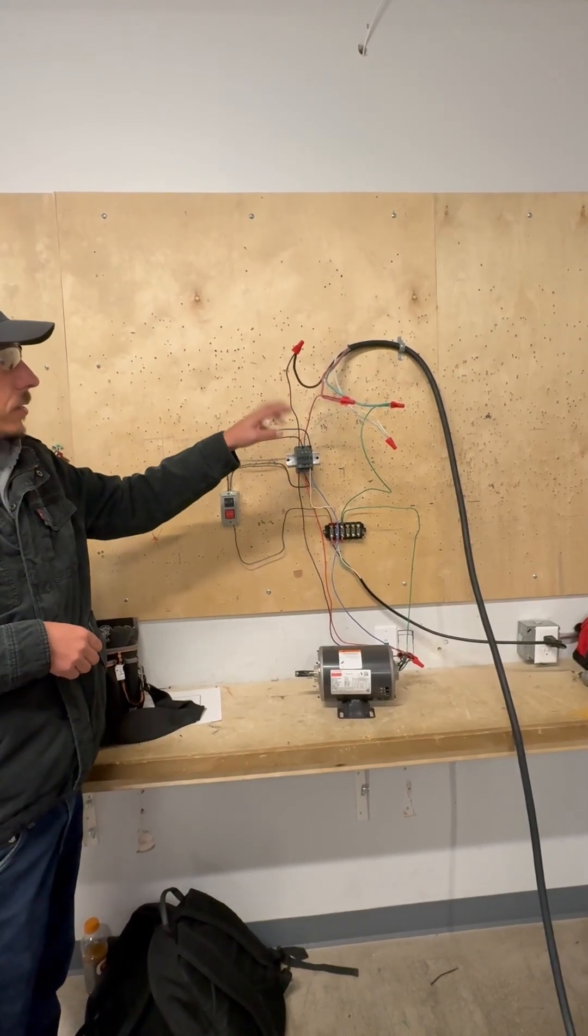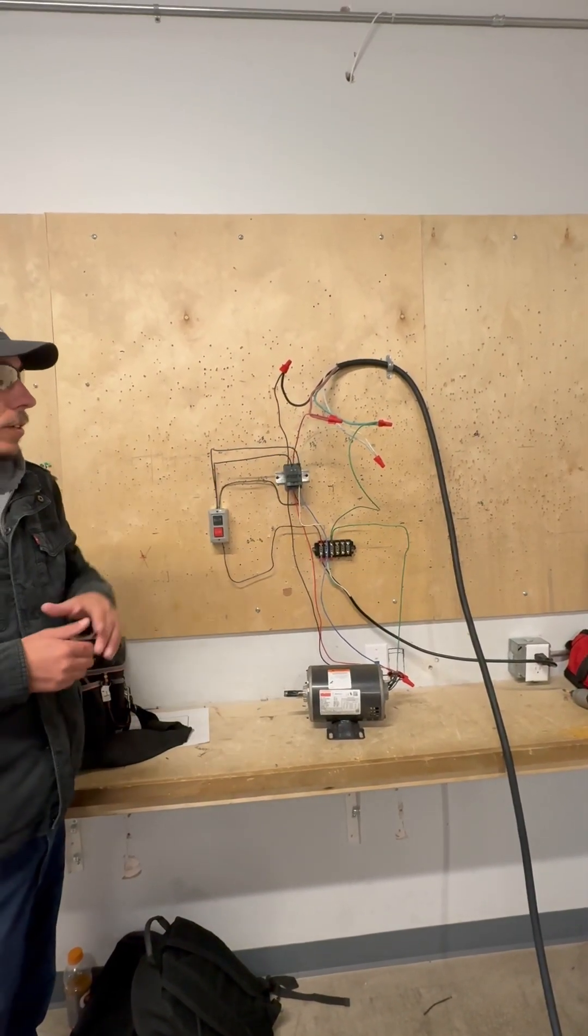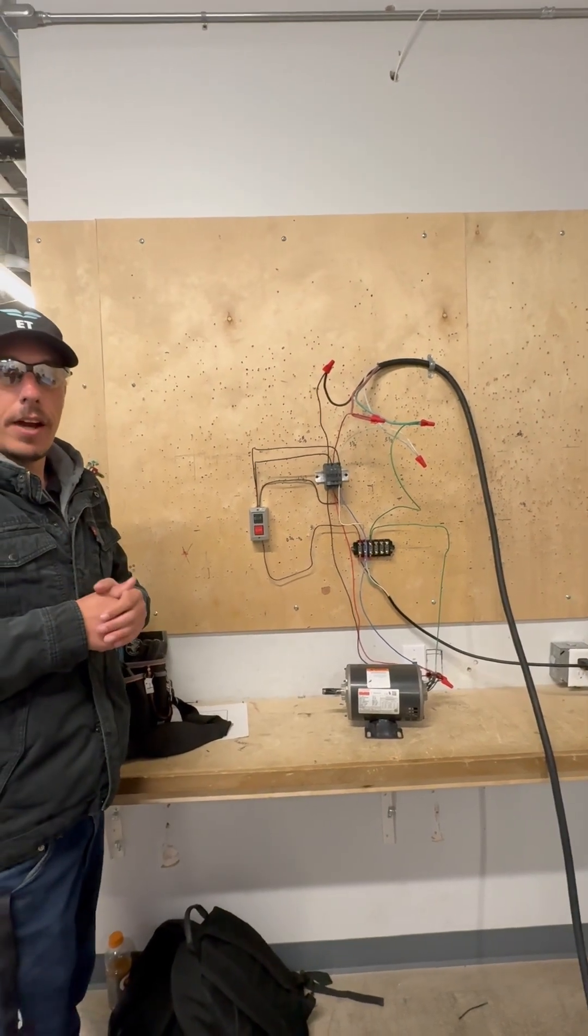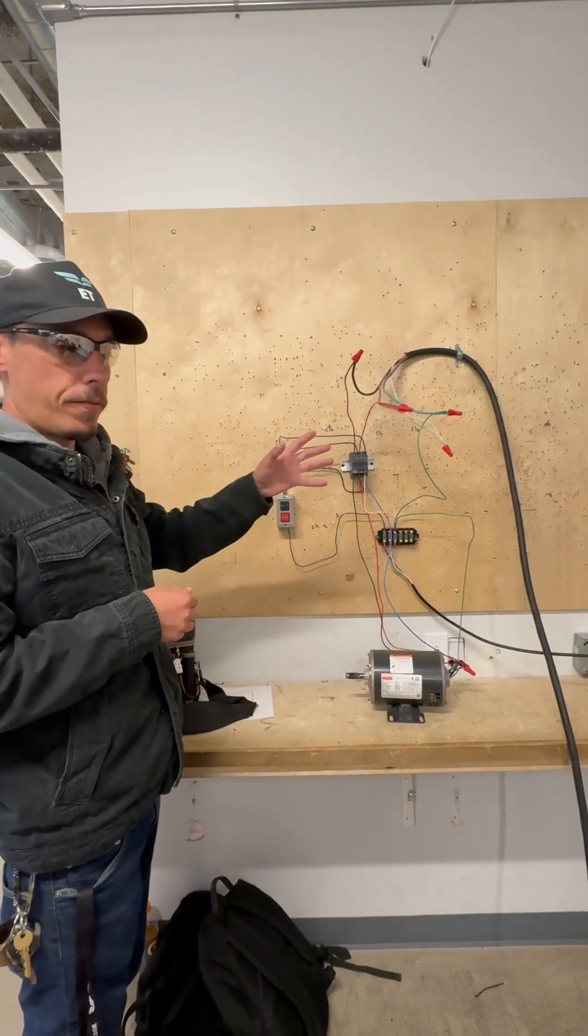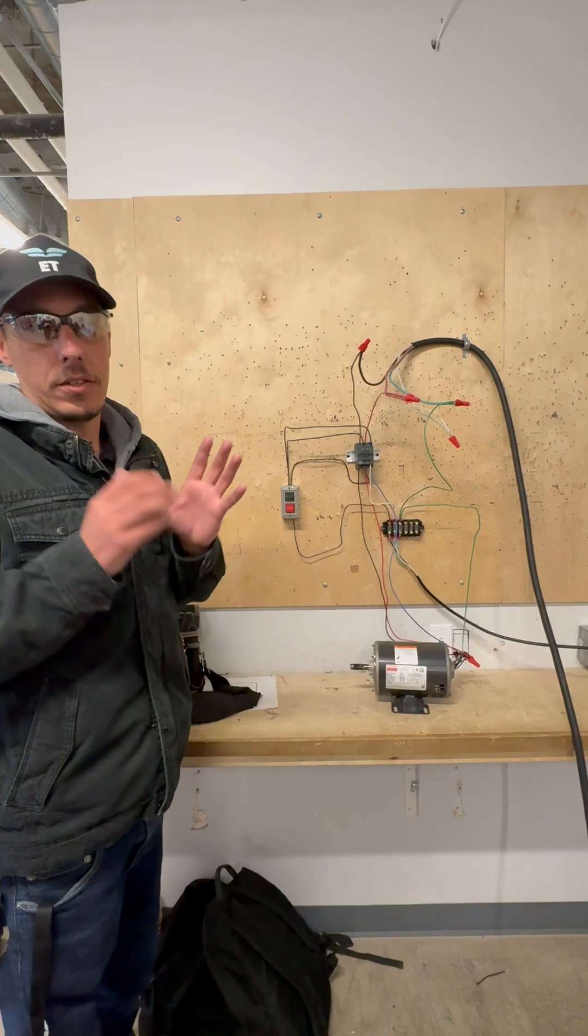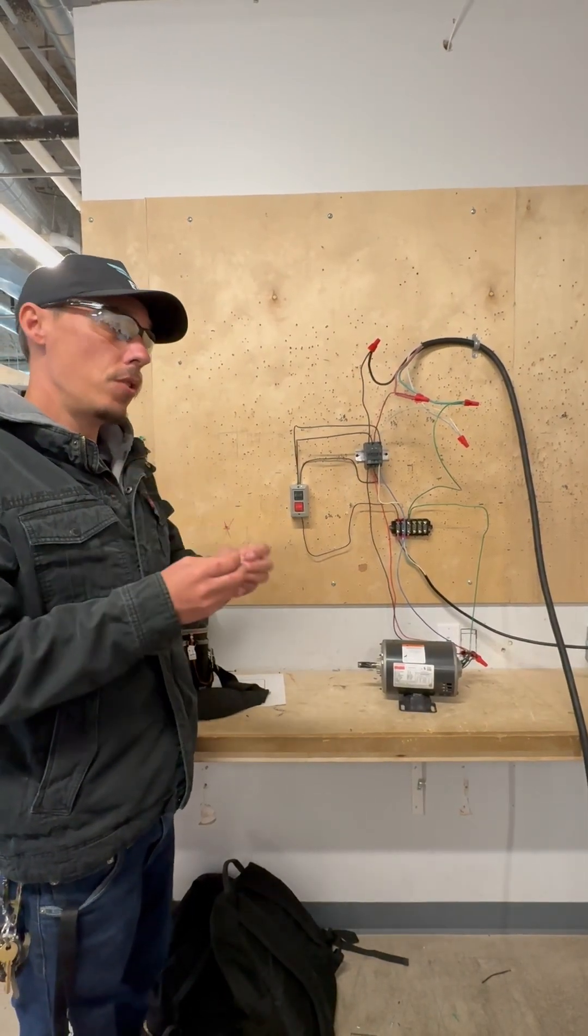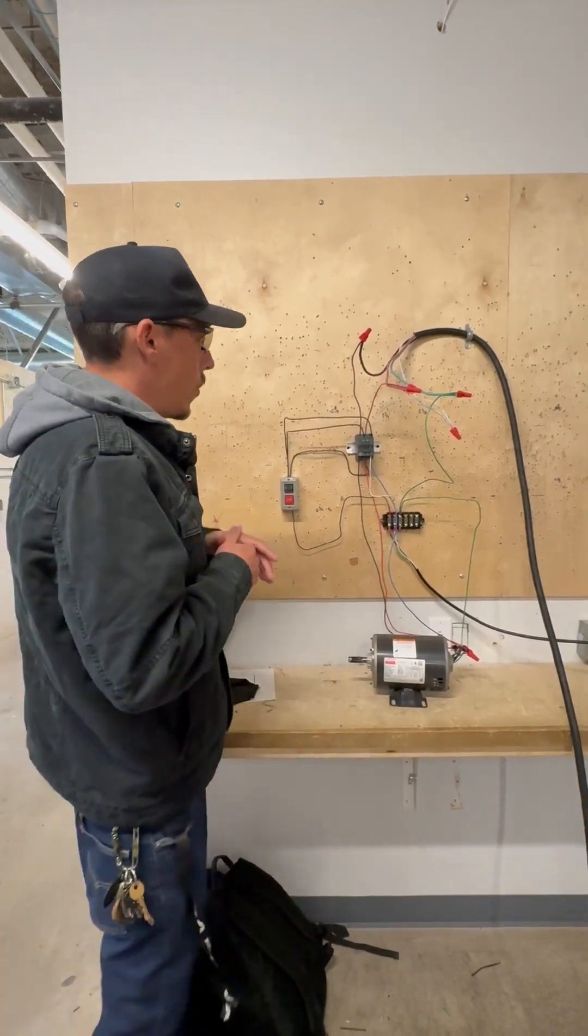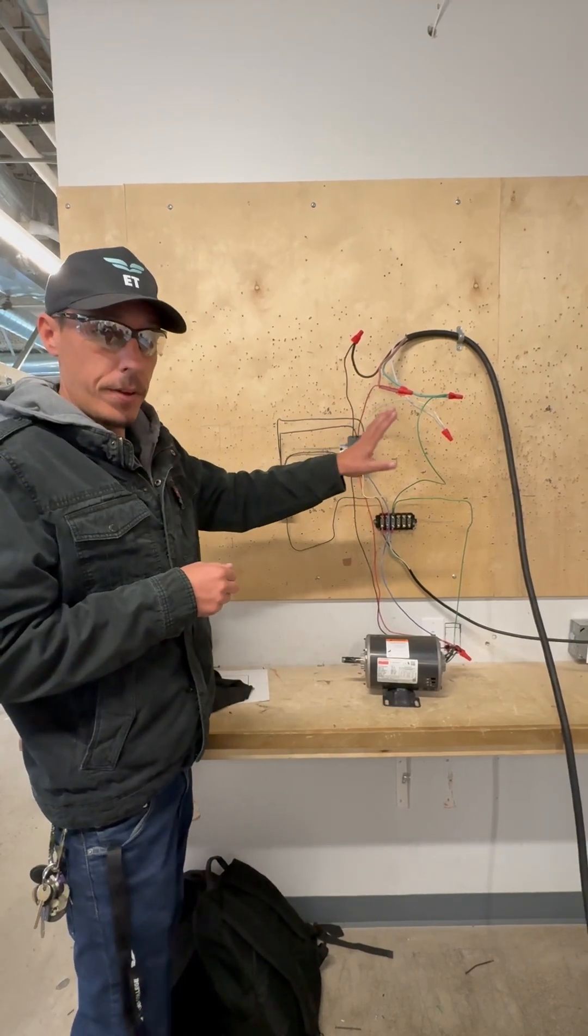If you notice the three-phase, it's black, red, white. So yes, white signifies a neutral, but in this case, three-phase, we don't need it as white. We're using the white as a hot. So in this case, that is okay for three-phase systems.